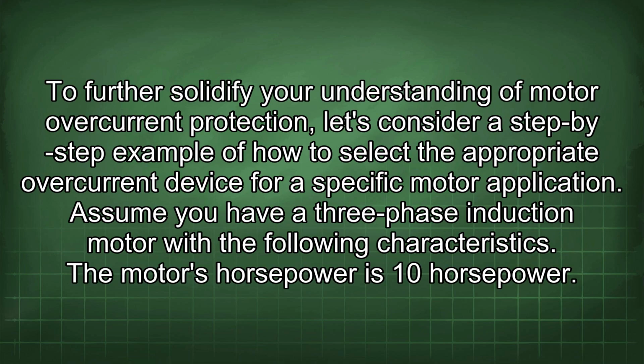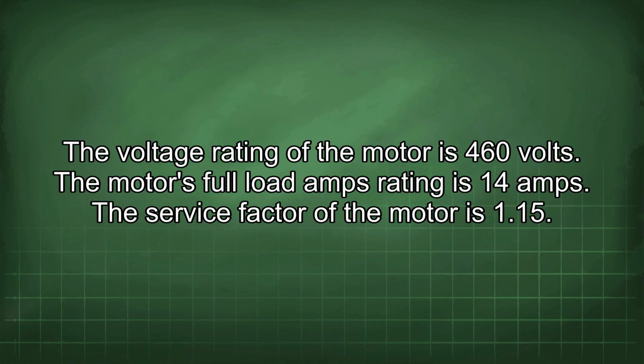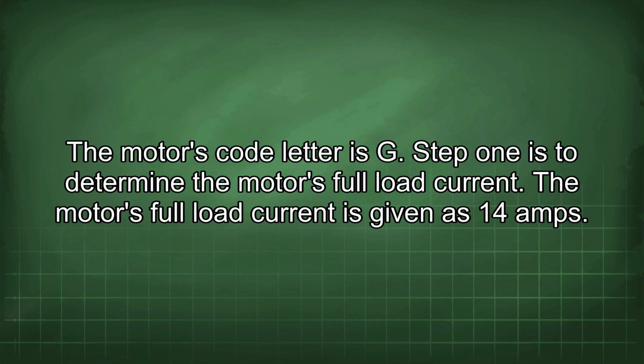To further solidify your understanding of motor overcurrent protection, let's consider a step-by-step example of how to select the appropriate overcurrent device for a specific motor application. Assume you have a three-phase induction motor with the following characteristics. The motor's horsepower is 10 horsepower. The voltage rating of the motor is 460 volts. The motor's full load amps rating is 14 amps. The service factor of the motor is 1.15. The motor's code letter is G.